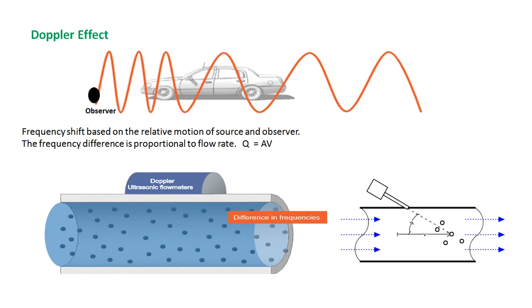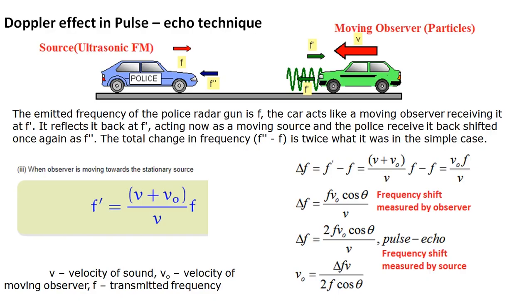In the simple case where the observer is moving towards the stationary source, the frequency observed is f' = (v + v₀) × f / v, where v is the velocity of sound, v₀ is the velocity of the moving observer, and f is the transmitted frequency. In our case, the ultrasonic flow meter using the Doppler effect employs the pulse echo technique.